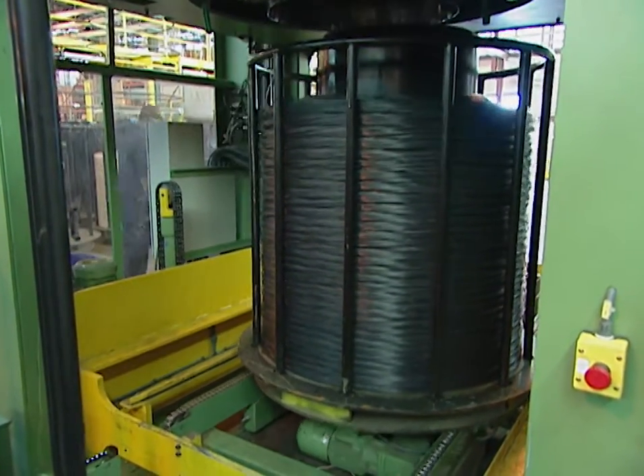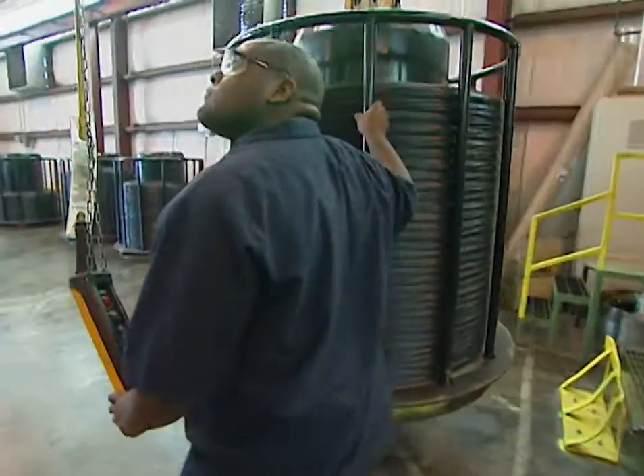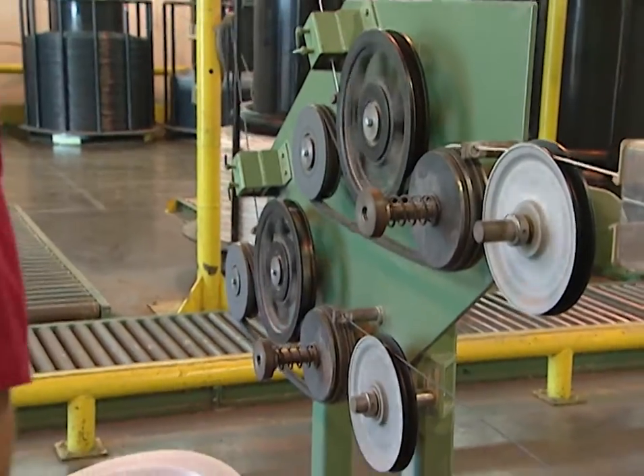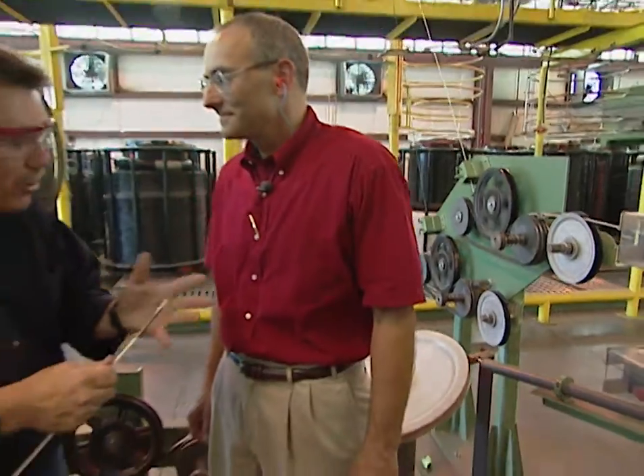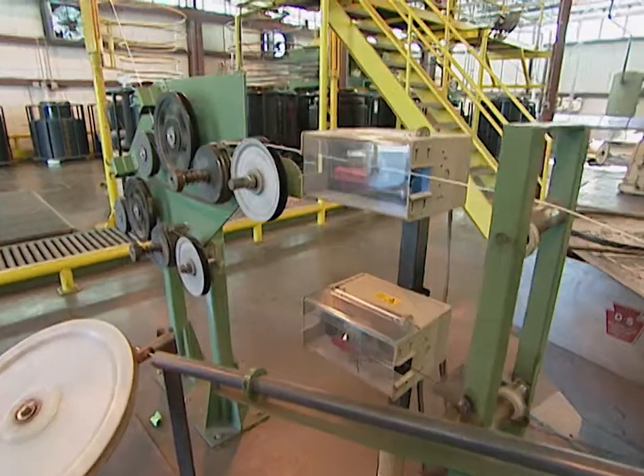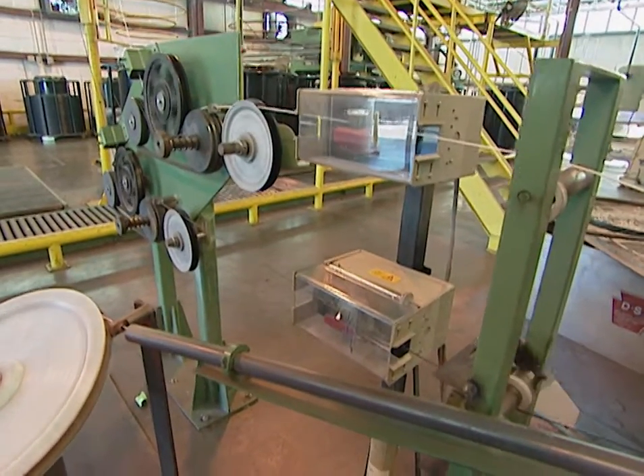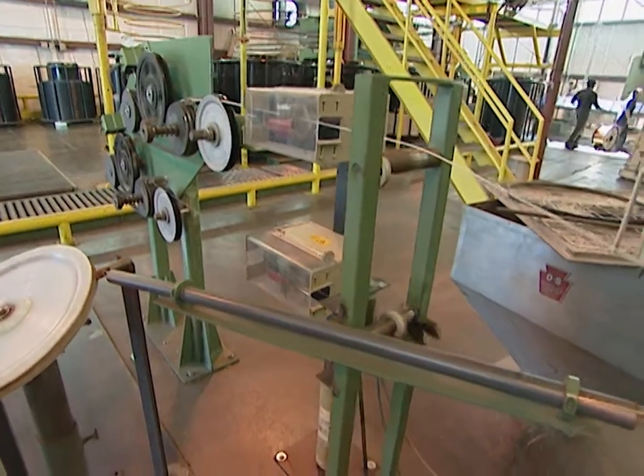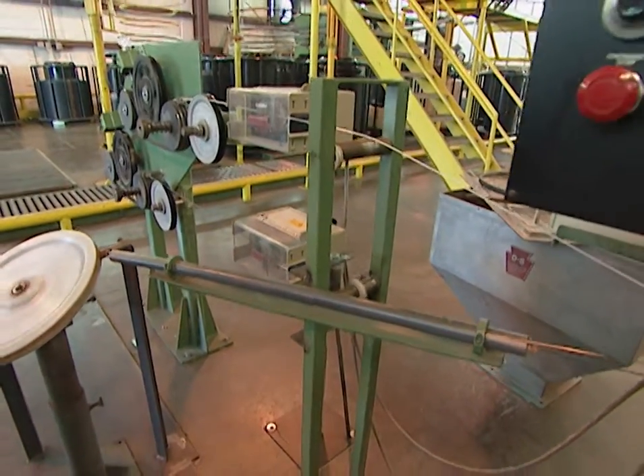The spools are then moved to the second leg of the production line for assembly of the Romex brand wire. To ensure there are no defects in the insulation, a sparker puts 4,000 volts across each wire. If there's a hole in the insulation, it would trigger the line to cut that wire out further down the line.